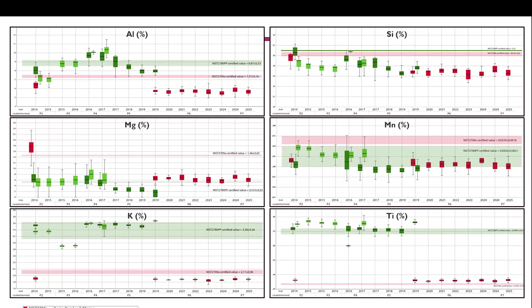For the major elements, we observe a systematic bias in the equipment results, where silicon and aluminum values are consistently underestimated. One of the reference samples also shows an underestimation for magnesium and manganese, while the other displays only a slight underdosage. Potassium tends to be underestimated and titanium overestimated in one of the samples. The second sample's values, however, for these two elements remain mostly within the certified range. For calcium and iron, the measured values fall within the certified range. However, chromium and nickel show a systematic bias of over or under quantification of values. Vanadium and strontium present mixed results, where one reference sample falls within the certified values, while the other shows a systematic overestimation.